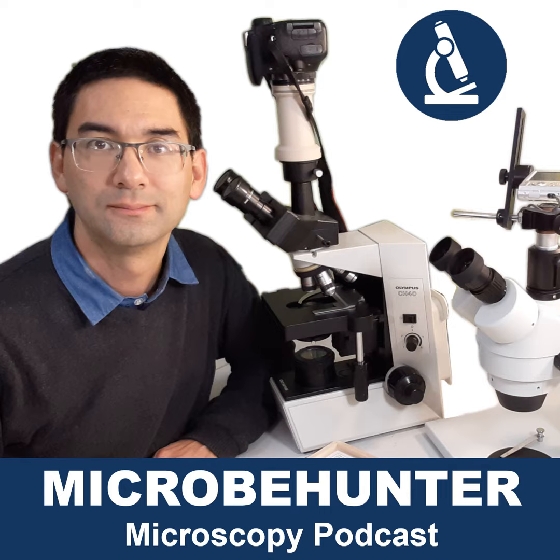So there are different possibilities, but for moving microorganisms I would only capture a video and then worry about getting the pictures out later, because by the time you've pressed the shutter button on the computer, it's already gone. A possible disadvantage is that the resolution of the video is lower than with still images, but that doesn't matter, because at that high magnification it's generally the microscope's resolution that is limiting. So any higher camera resolution is not going to give you more image information anyway. I would say just go for video and worry about the pictures later.